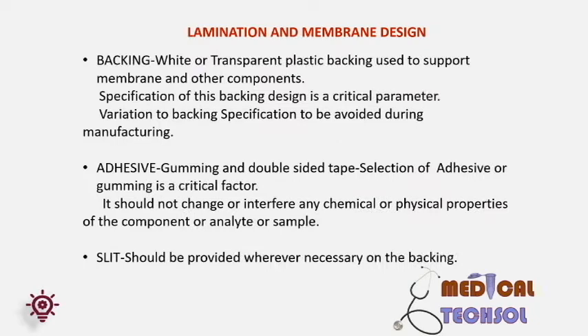Lamination and membrane design: three major components are plastic backing, adhesive, and release liner. The backing is white and non-transparent, though sometimes transparent backing is used to support the membrane and other components. You should not confuse this with the transparent plastic support used to cast the membrane. Backing thickness should be consistent, and specification of backing design is a critical parameter — small changes may lead to significant result changes. Variation in backing specification must be avoided during manufacturing.